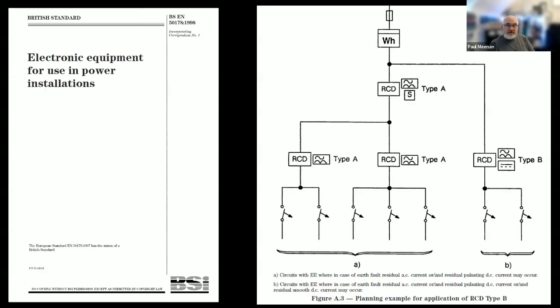Now, I wanted to give you a few little gems, little nuggets, really, to bookend Krish's excellent webinar. The picture says it all. BS EN 50178 in 1998 clearly showed that if you had something where DC pulsating current could occur, you would configure the installation in your board separately. So you've got type A RCDs protecting circuits, a time delayed RCD to ensure you have selectivity, but separate to that, a type B, which gives you more immunity to DC. And if there was leakage, it wouldn't saturate or blind the type A.